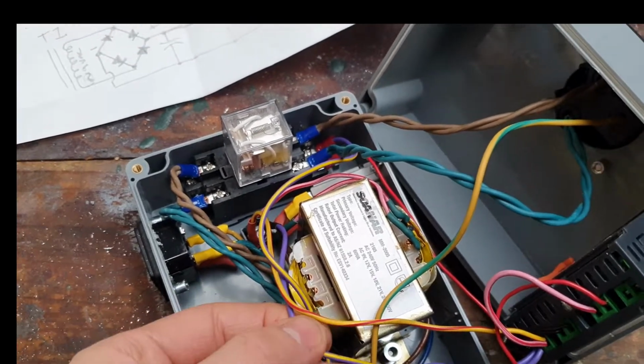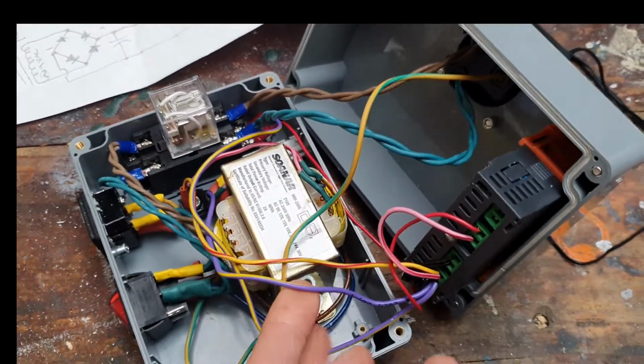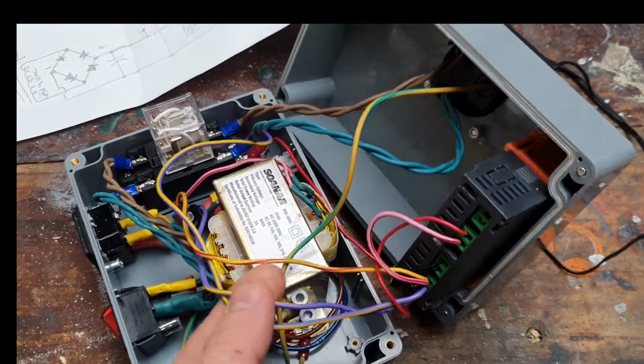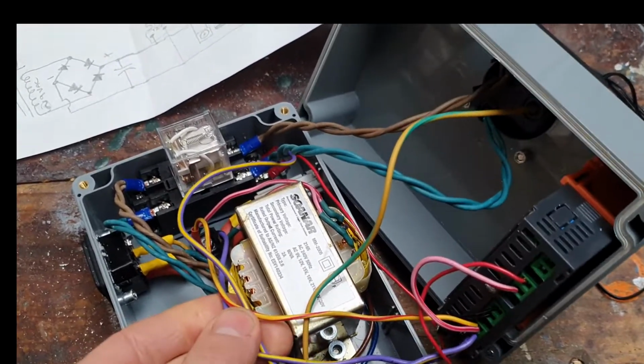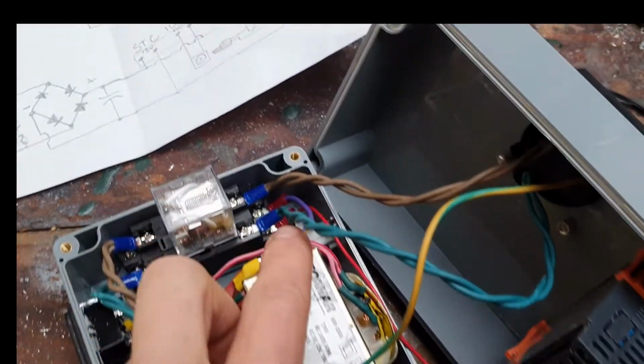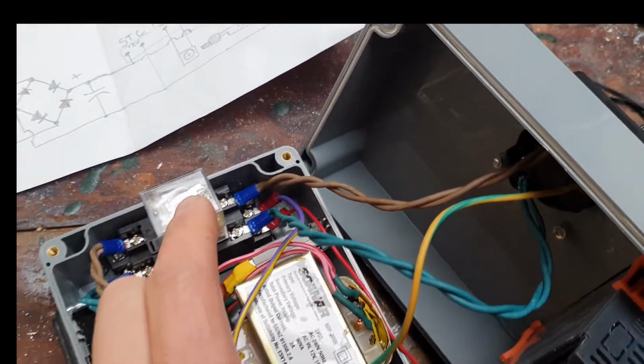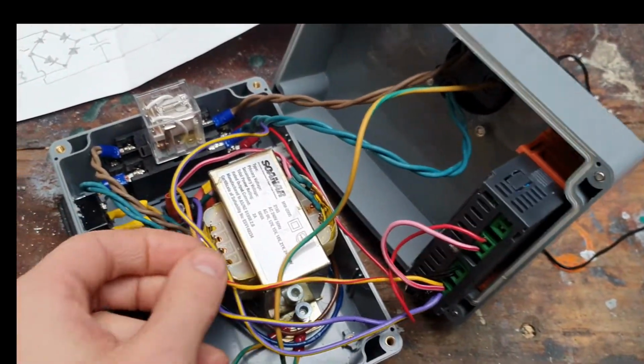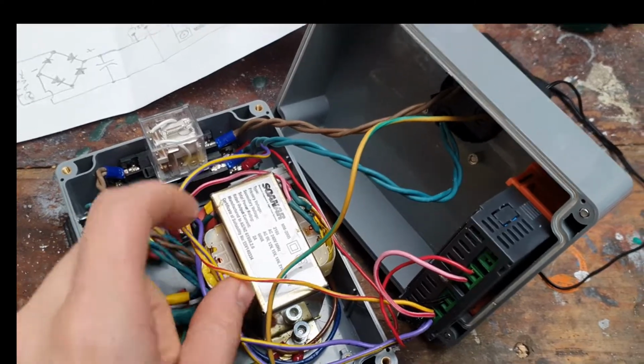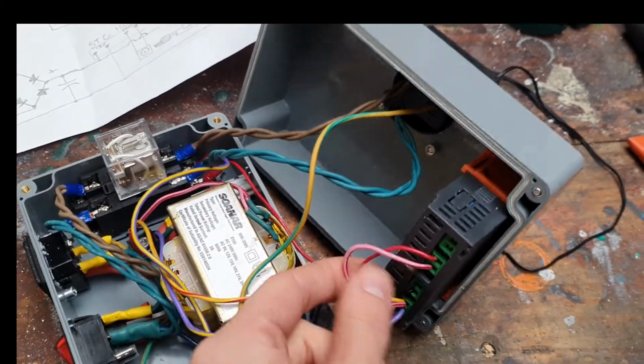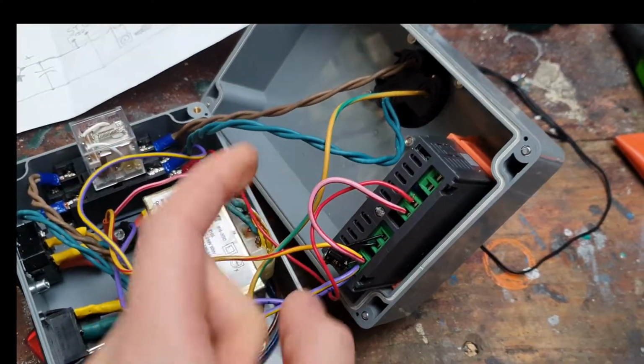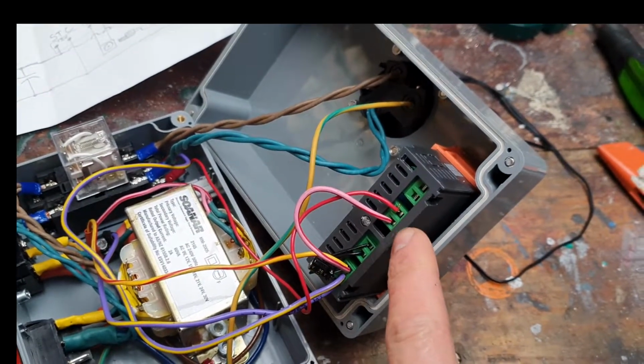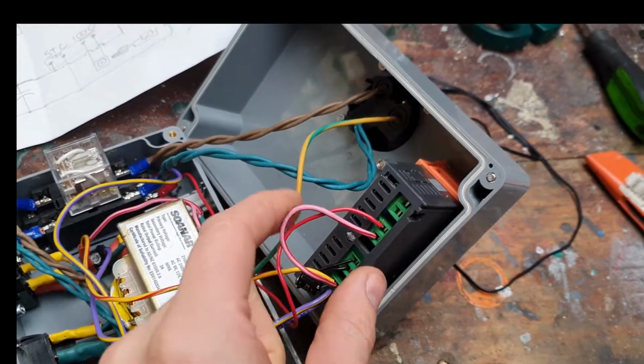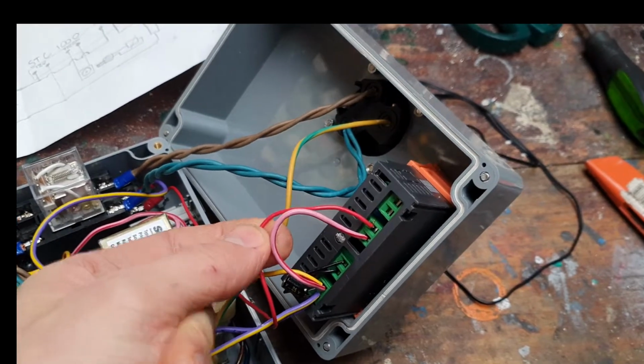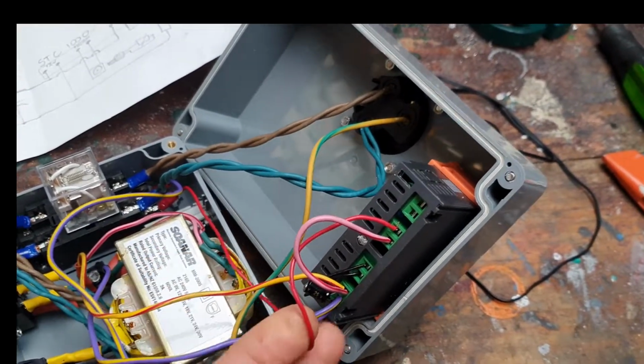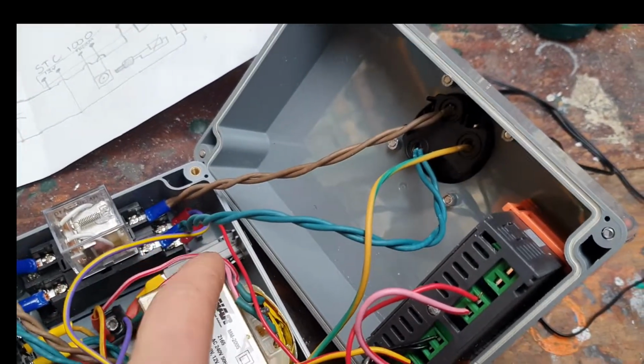The negative of the full bridge rectifier is split to the STC controller on this purple and yellow wire, and then the other purple and yellow wire goes to one side of the relay coil. The positive output of the rectifier goes to the STC controller and is also bridged across to the heater switched output, and the other side of the heater switched output on this red wire goes to the other side of the relay coil.